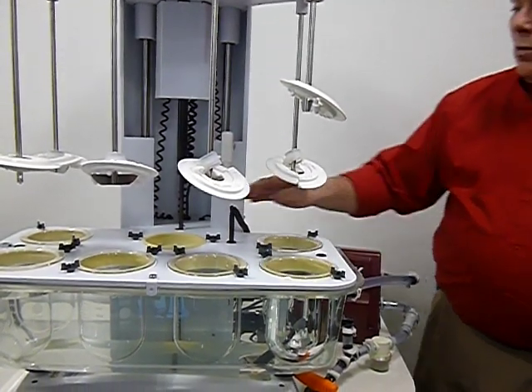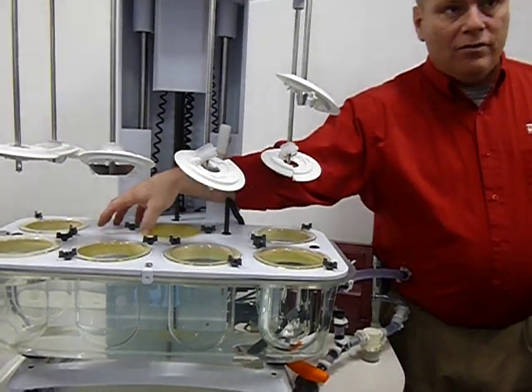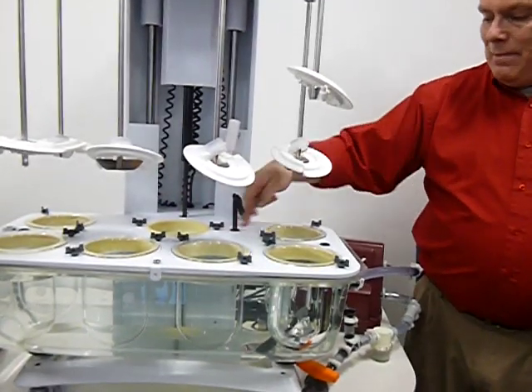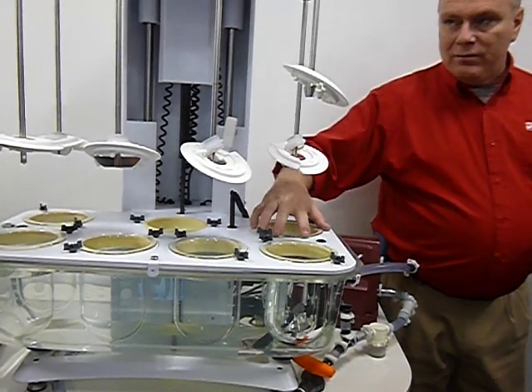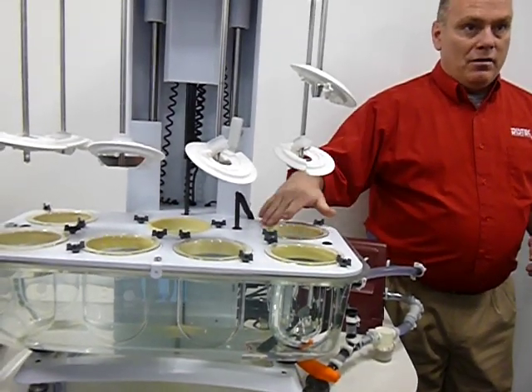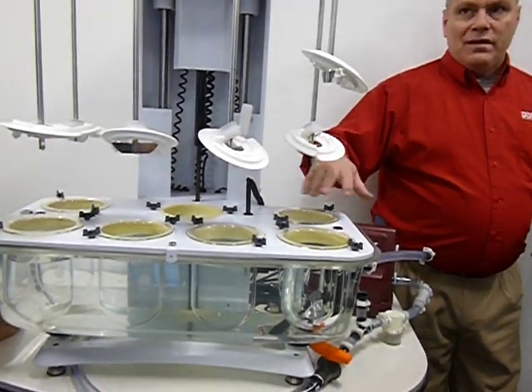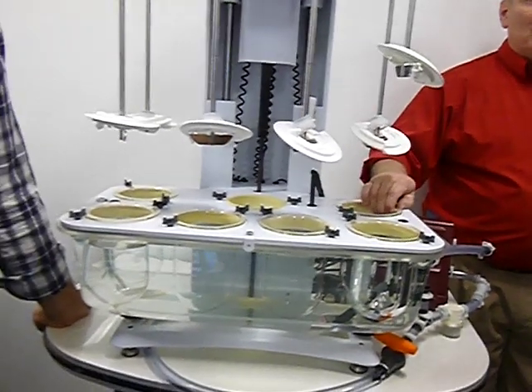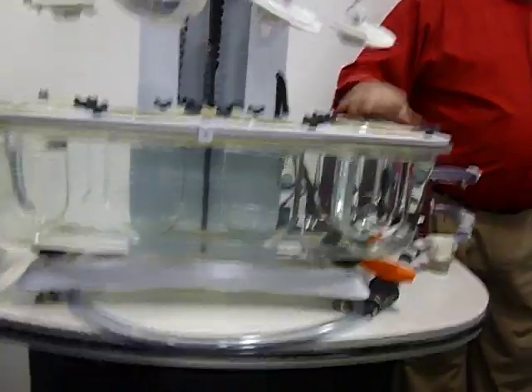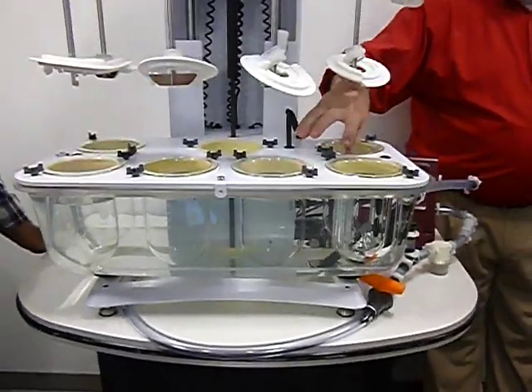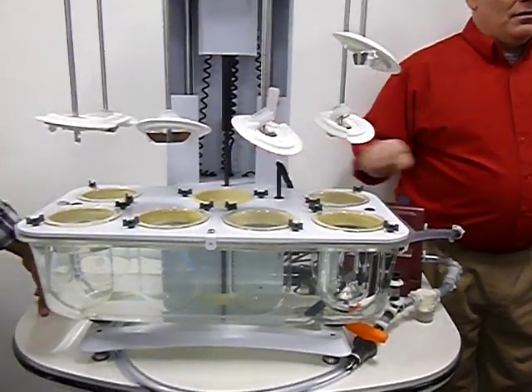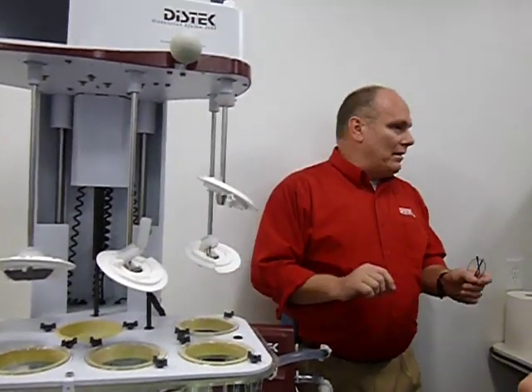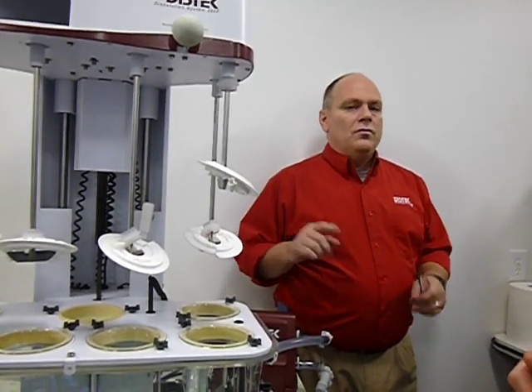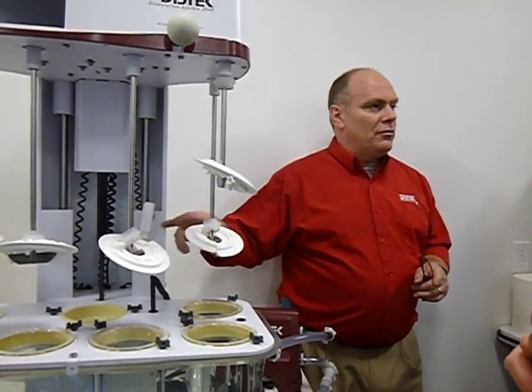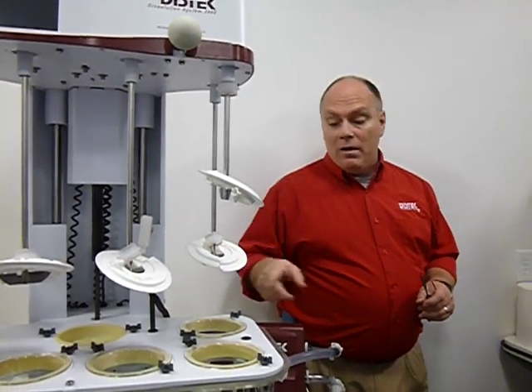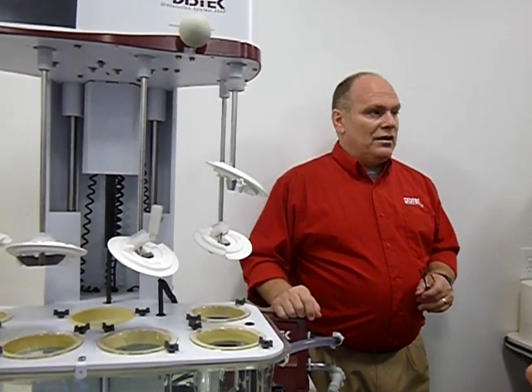When it's going off at an angle, and you have a position here or 2 positions here, a 6th, 7th, and 8th position, it's hitting it and bouncing it back this way. We've noticed that we've had some temperature differences on this one right here, higher than the others. It causes a temperature degradation in here, and it also causes additional wobble in this one. Our results for chemical testing always seem to be different on this end than down at that end over there. Very minor, not failing, but there are some differences. So if you do encounter any problems with a 2500, if you have a 7th or 8th position 2500, that's something to bear in mind, that perhaps the circulation in it has changed.